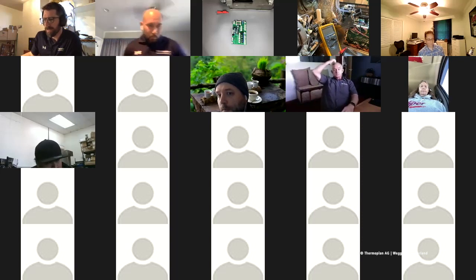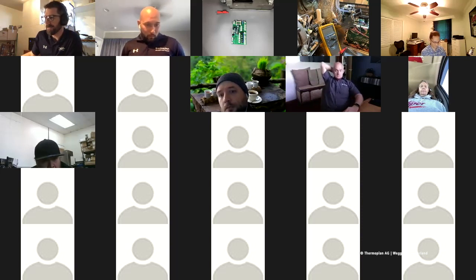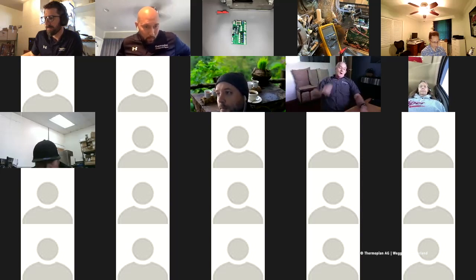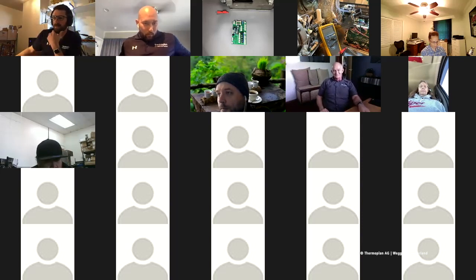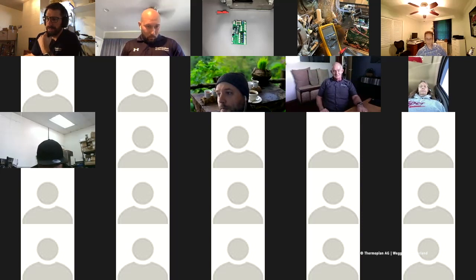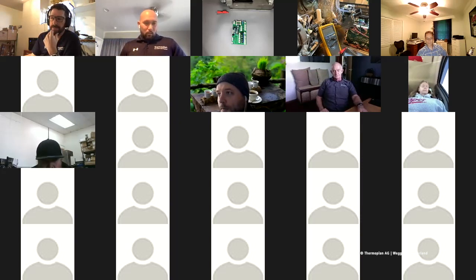iPhone, there's like six of them, I'm sure, but somebody said, sounds like you still have to check the boards with a meter. And then Todd says, -1 degrees on the brew chamber heater indicates a missing brew chamber NTC circuit. Yes, you basically have an open circuit for the NTC. If the power board or the component control board can't see the NTC, it will give a -1.